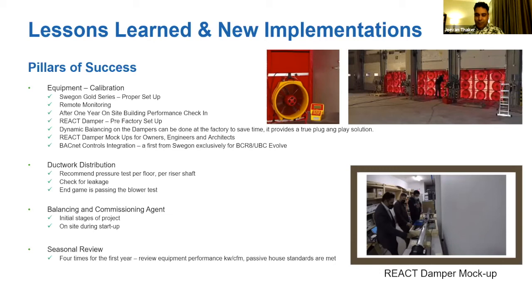On Passive House projects, I think people forget. Think about our unit. This unit is probably 3,000 CFM. Each suite is getting about 110 CFM. When you have leakage of 1%, 2%, 5%, whatever it is, it's significant. So one takeaway for me, for sure, again, out of our scope, but because we have these early setup meetings with the whole construction team, is don't wait till the end of the project to test your ductwork. I've heard of a lot of projects where only the main branches are tested, or maybe just the riser. I highly recommend testing more; you're going to save in the long run and get your project commissioned quicker. Test your main branch, test your risers. There are ways to do that, and it'll get you on the right path.